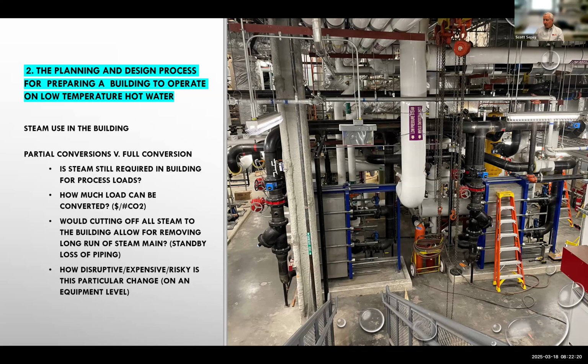After determining which equipment has aged out and needs replacement and whether you need to keep some steam for processes, you need to evaluate the viability of the remaining heating equipment. And this is a picture of one of the science buildings in the middle of a conversion. You can see the original steam main coming into the shell and tube heat exchangers. The new plate and frame heat exchangers are in place, and we're going to demo the white heat exchanger in the near future.